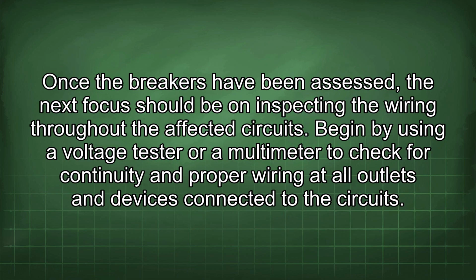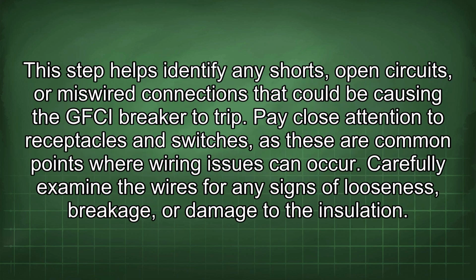Once the breakers have been assessed, the next focus should be on inspecting the wiring throughout the affected circuits. Begin by using a voltage tester or a multimeter to check for continuity and proper wiring at all outlets and devices connected to the circuits. This step helps identify any shorts, open circuits, or miswired connections that could be causing the GFCI breaker to trip. Pay close attention to receptacles and switches, as these are common points where wiring issues can occur.